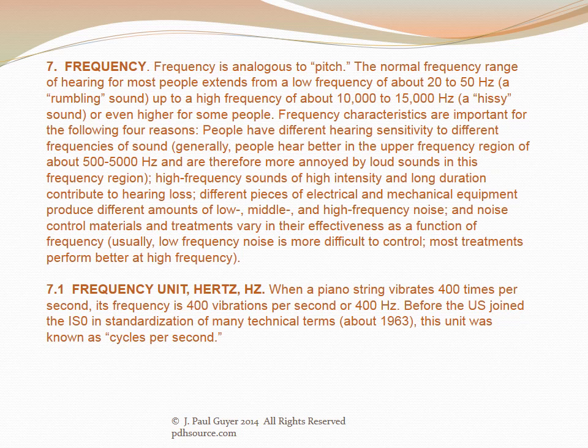Frequency is analogous to pitch. The normal frequency range of hearing extends from about 20–50 Hz (a rumbling sound) up to about 10,000–15,000 Hz (a hissy sound). Frequency characteristics are important for four reasons: people have different hearing sensitivity at different frequencies (best around 500–5,000 Hz); high frequency sounds of high intensity contribute to hearing loss; different equipment produces different frequency distributions; and noise control materials vary in effectiveness with frequency — low frequency noise is generally more difficult to control.